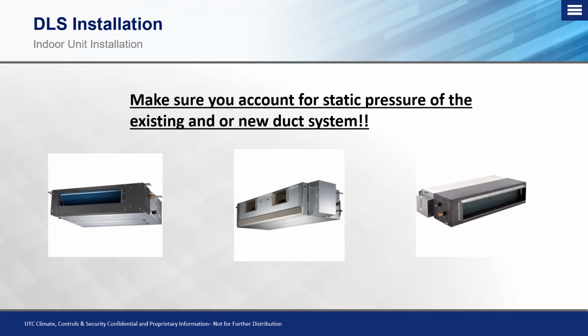While the larger style ductless units that can do just about 0.4 inches of static pressure max can facilitate a couple of takeoffs if you're trying to condition multiple spaces off of one ducted ductless indoor unit. So please make sure that you account for that and that you don't run into any issues during any future installations. And of course, if you have any questions on something or you can't find literature that will give you that information, you can always call me or one of the guys in technical service here, and we can give you that information so that you can make an educated decision.